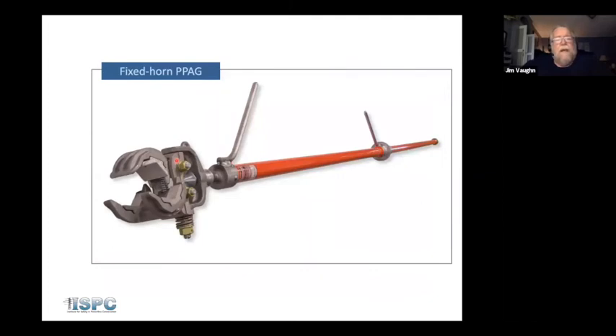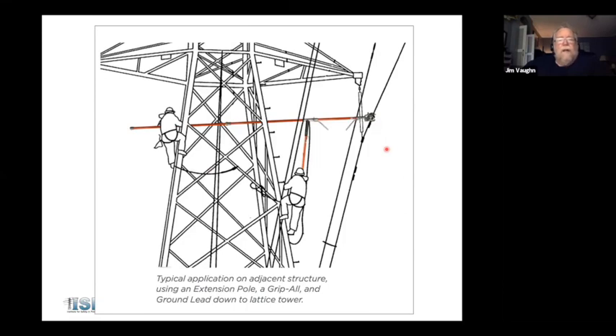This is a fixed PPAG. This is the conventional, or the contemporary, type of PPAG. And what you see here is the arcing horns. You fix it to the structure at the grounded end. You fix it to the conductor at the hot end. The probe, the horn, is hot. The air gap will not flash over unless the voltage reaches a maximum value, and then it will flash over. And on this end, there also is a lead. This is where your ground connection takes place. So it looks like this. Now, of course, you see them making the ground connection now that the PPAG is in place. You see that air gap that's created here at this location.